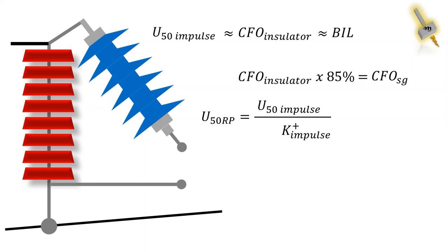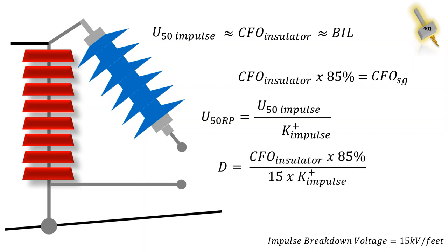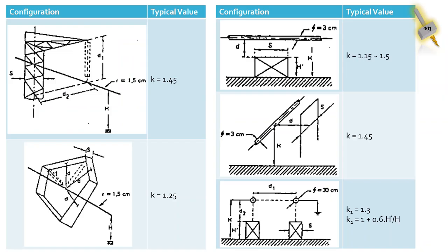Generally, it is accepted that impulse breakdown voltage of air is 15 kV per feet at standard temperature and pressure. Reconfiguring all the above formulas, the maximum spark gap is CFO insulator multiplied with 0.85 divided by gap factor and impulse breakdown voltage of air. These are some of the gap factor for converting rod plane electrode configuration to other electrode configuration.